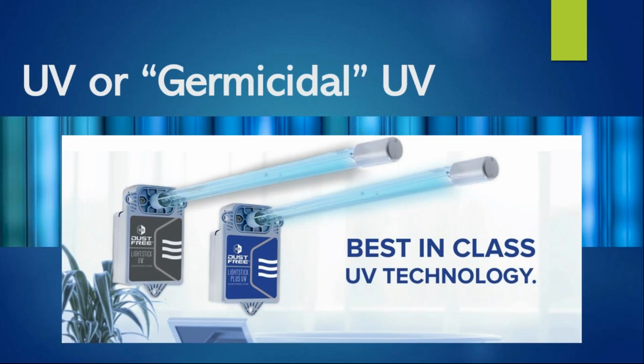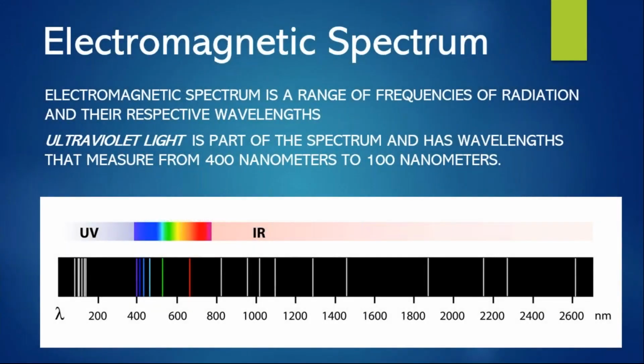And for years, we used to put those in the return air drops and call them air purifiers. So just be careful of some boxes and labeling that you see out on the market. They'll have a UV lamp and they'll say it's an air purifier, when technically it really isn't doing anything actively for the air that we breathe. However, it'll help you keep coils clean and the HVAC system from becoming a source of a problem.